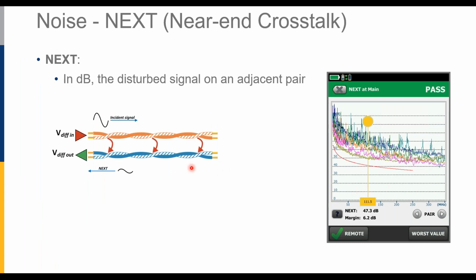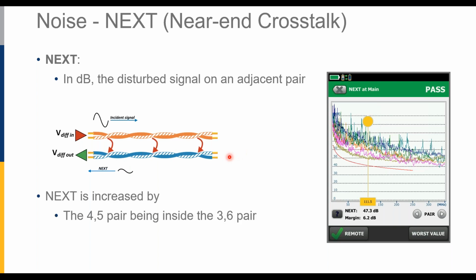All right, another noise parameter is near-end crosstalk. This is interference that goes from one cable to the adjacent cable. In the olden days, when we had phones in our houses, you could pick up a phone and sometimes you'd hear your neighbor talking. The same thing happens in the cable, where some signal is induced from one of the pairs to an adjacent pair. So we'll inject a signal on one pair, and if we listen on the adjacent pair on the same side, we'll get near-end crosstalk. If we listen to that adjacent pair on the far side, we get far-end crosstalk.